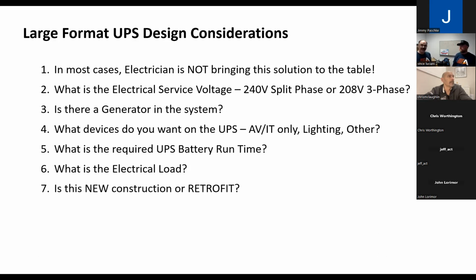We also ask if it's new construction or a retrofit. Most of the projects we've dealt with over the last several years were retrofits where we put large format UPSs in, say there was already a 60, 80, or 100 amp feed going to the rack room. We can create a critical load panel if needed to adjust for sizing, making sure only the AV ends up on the output of the UPS, bringing in that Romex, intercepting it, and routing it through the UPS to a critical load panel or existing sub panel.